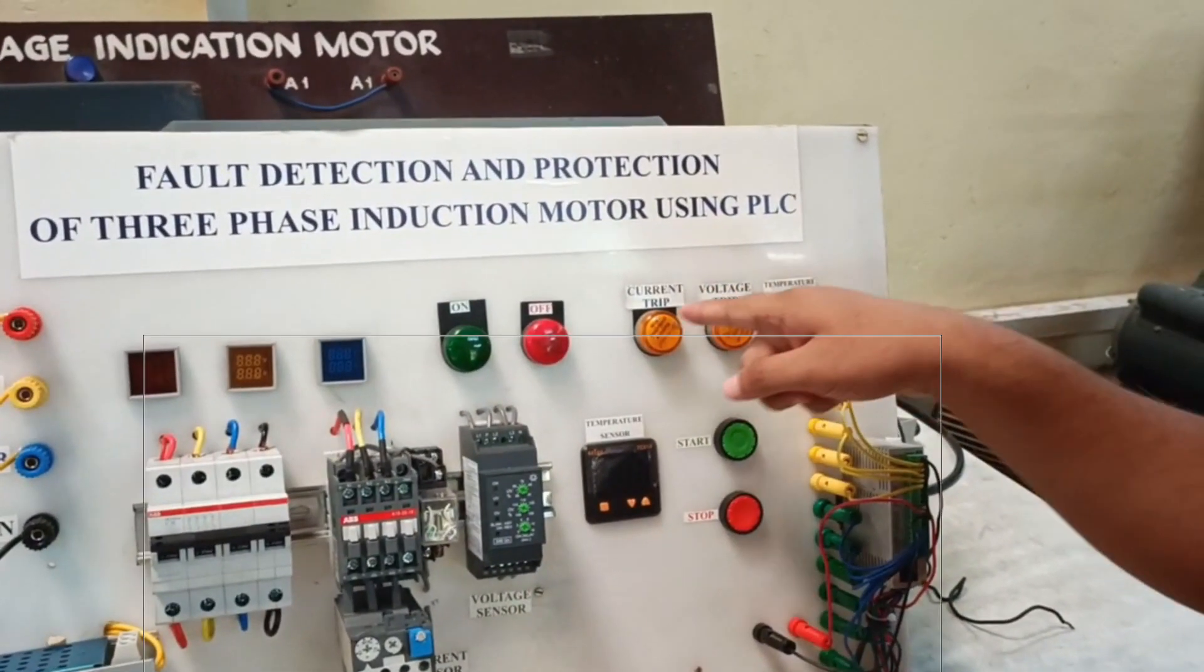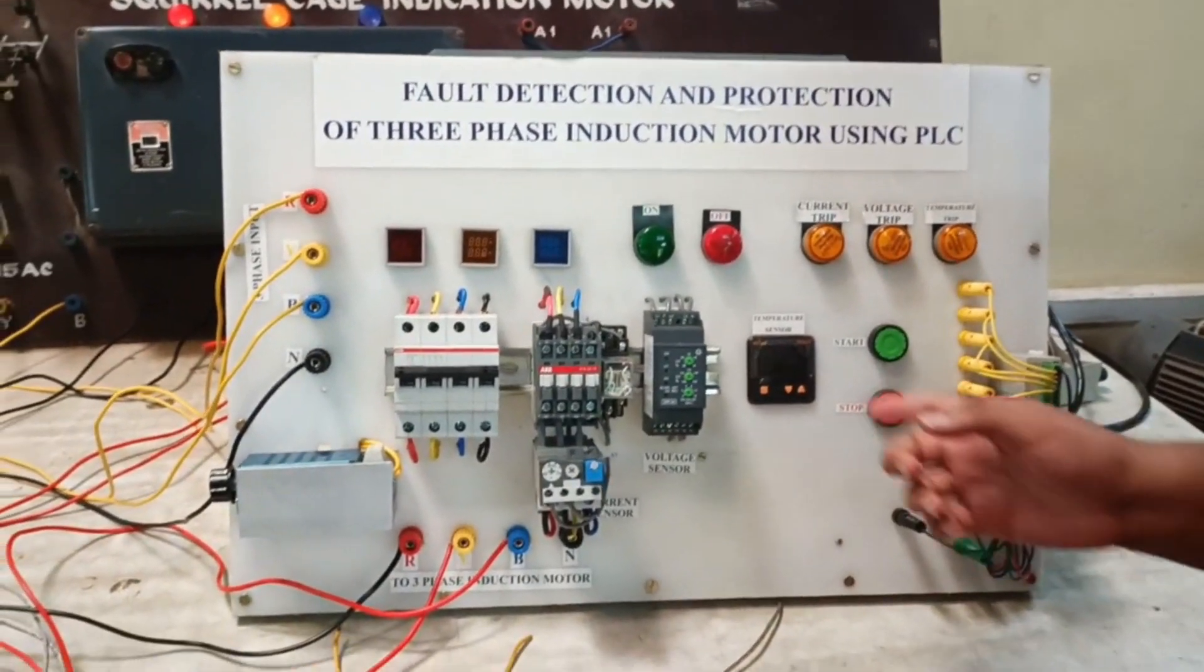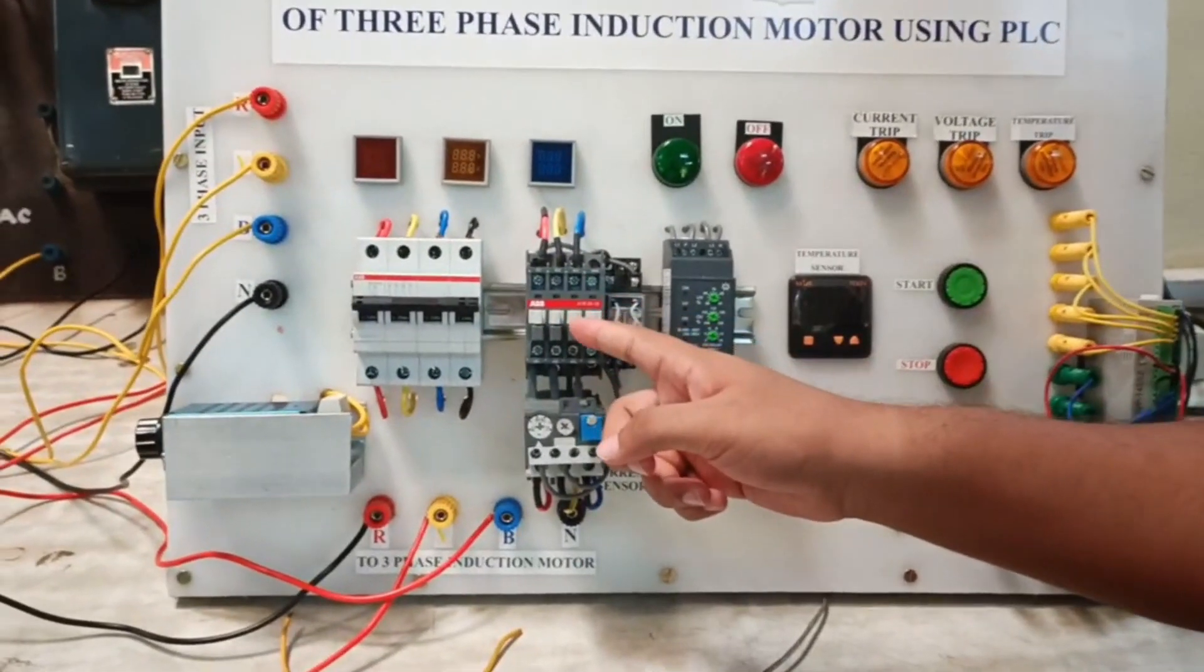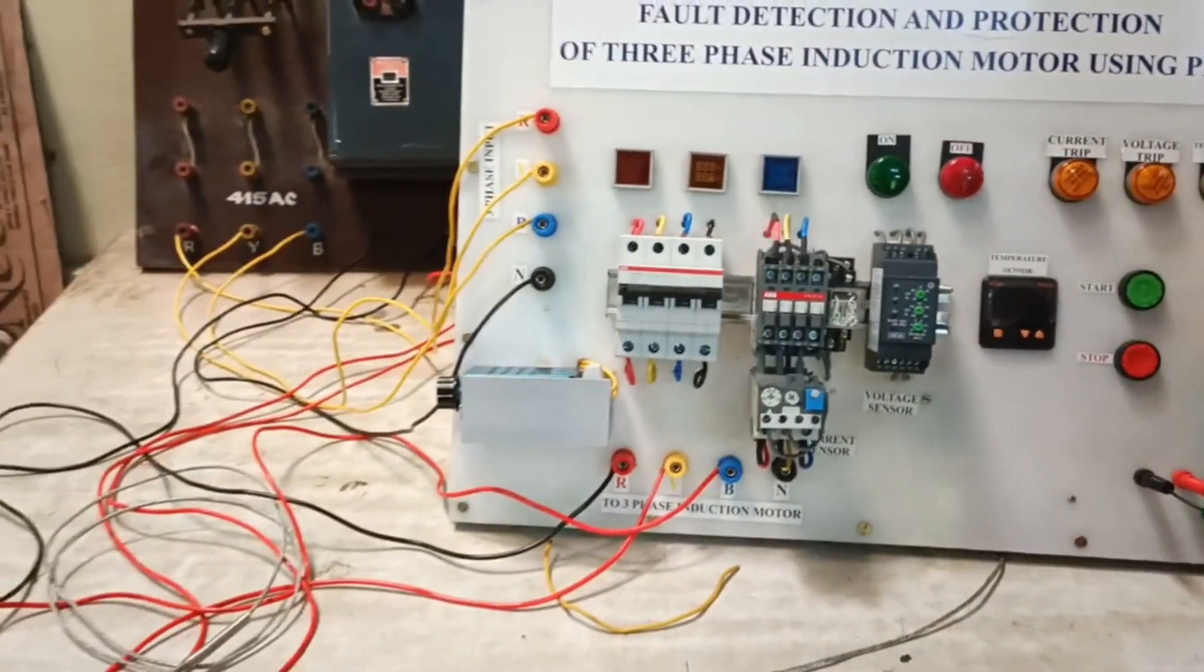So this PLC we are using 6 outputs, 2 for the on and off indicators and 3 for the current fault, voltage fault and temperature fault indicators. Then the last output goes to this 3 phase AC contactor. This contactor is used to turn off the induction motor in case of any of these faults.